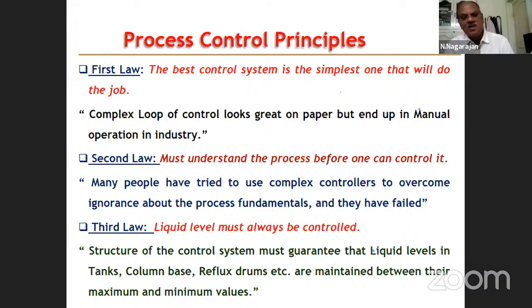The third law is, liquid level must always be controlled, because liquid level is one dangerous parameter. If it is not controlled properly, either the vessel will be emptied or the vessel will be overfilled and leads to pressure build-up problems or spillage problems, all those things will happen. So liquid level is one important parameter. Mainly wherever we have liquid hold-up, vessels, tanks, columns, reflux drums, the liquid level must be very carefully controlled.